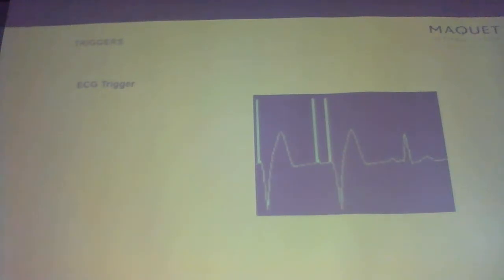EKG trigger. If they have a pacer, which is not uncommon, for someone to have a temporary pacemaker and have a balloon pump, it'll identify that. It can pick that up. It looks for the R wave to trigger off of. Recommended for your arrhythmias, paced rhythms as well. So EKG as your trigger is your primary one. If it needs to trip to pressure, it will.